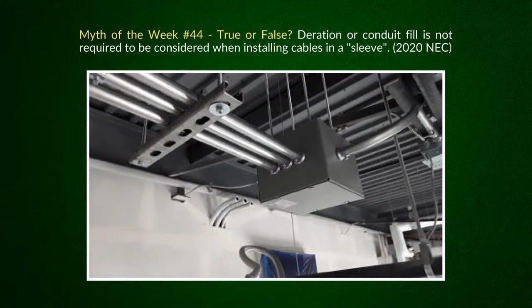But the whole thing is, what do you think the fill is based on? You could fill it to 100%, but then there isn't adjustment needed, and I'll explain why, because of what NFPA actually says. Note 2 says Table 1 only applies to complete conduit or tubing systems. That means it's complete from end to end. A sleeve is not complete from end to end; a nipple is complete from end to end. That's right, and when you brought this up, that was the first thing I told you: it has to be complete on both ends, otherwise it's not a raceway.